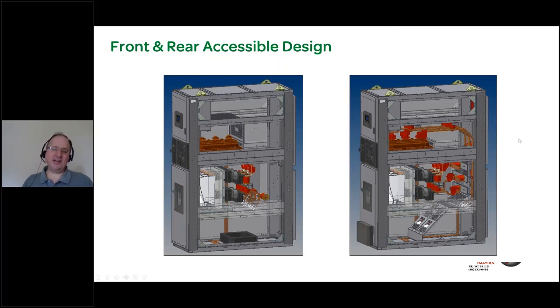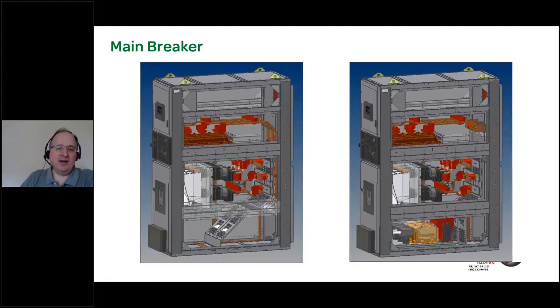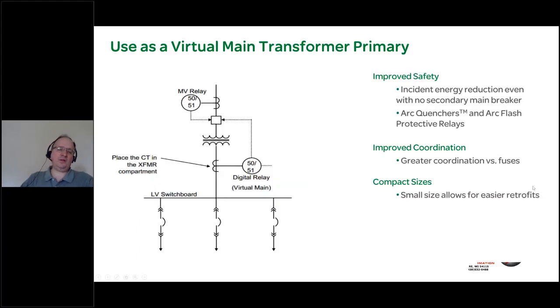So we could do a side termination compartment even with a draw out switchgear in this design, and put the equipment against a wall and save that rear aisle space. This shows a detailed view of the main breaker. This particular one you're looking at here is for the fixed mount design, not the draw out design. This type of hybrid metal enclosed switchgear is absolutely perfect. It's the ideal equipment to serve as the transformer primary disconnect and create a secondary virtual main.